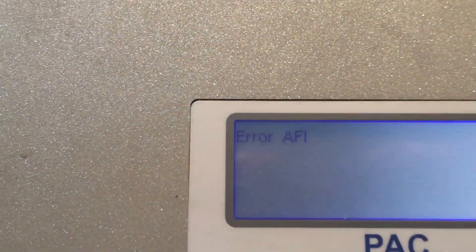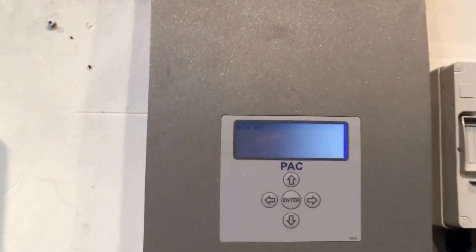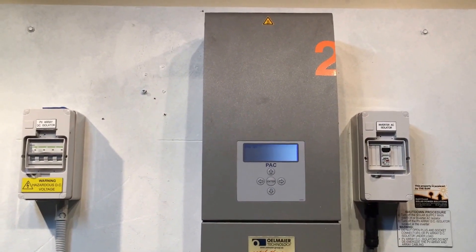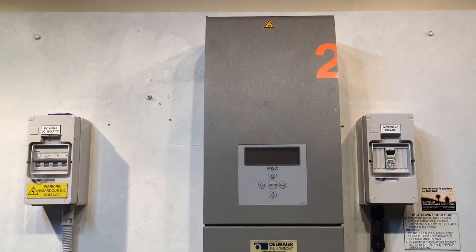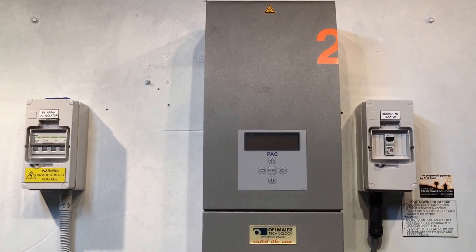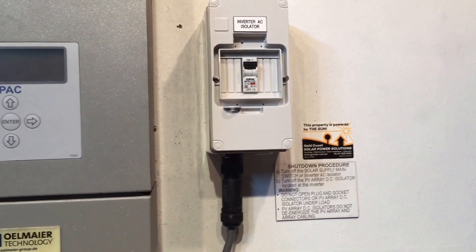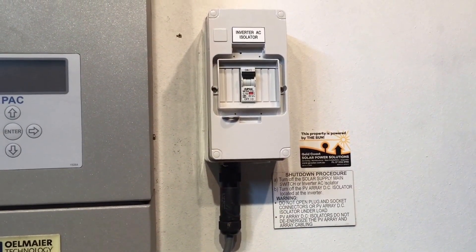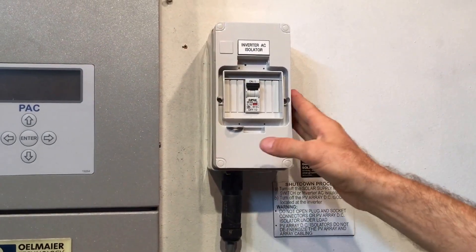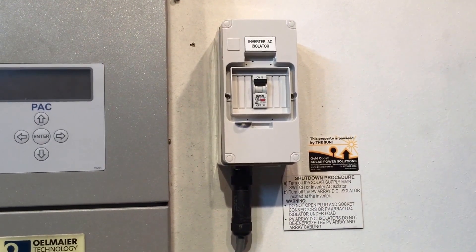So unfortunately, if your Oelmaier inverter is coming up with this error AFI, it is going to be a replacement job. You can try rebooting the system to see if that changes anything, though very rarely does it actually help. If you do want to try that, it's always important to follow the shutdown procedure: turn off the solar supply main switch or the inverter AC isolator. The solar supply main switch is always located in your switchboard. The AC isolator, if present, will be beside the inverter like this one here — turn that off first, then turn off the PV array DC isolator located at the inverter.